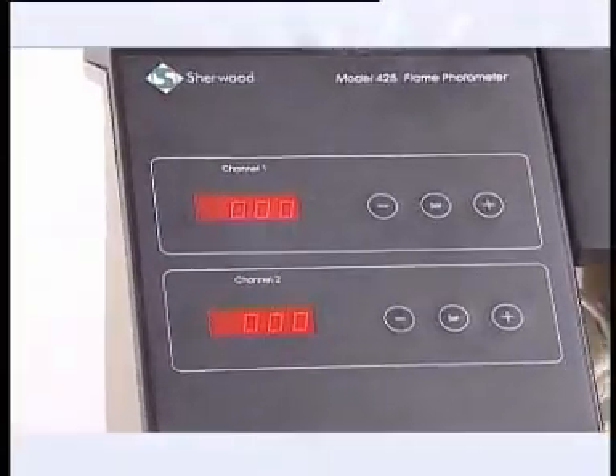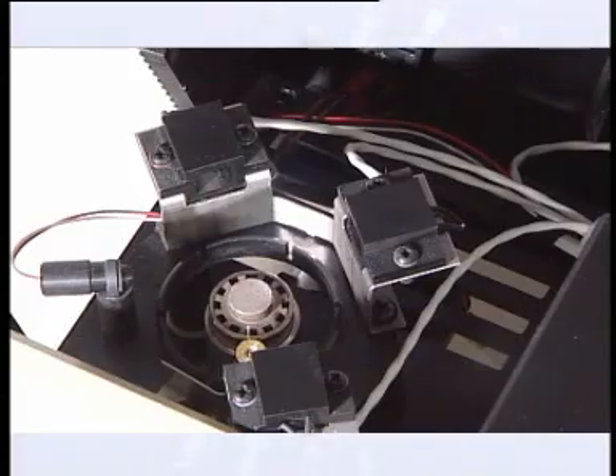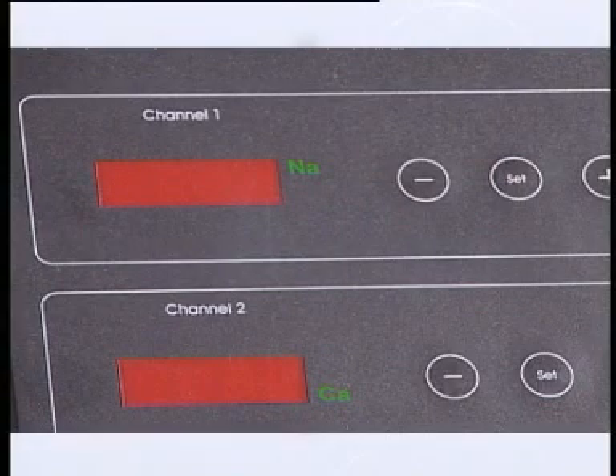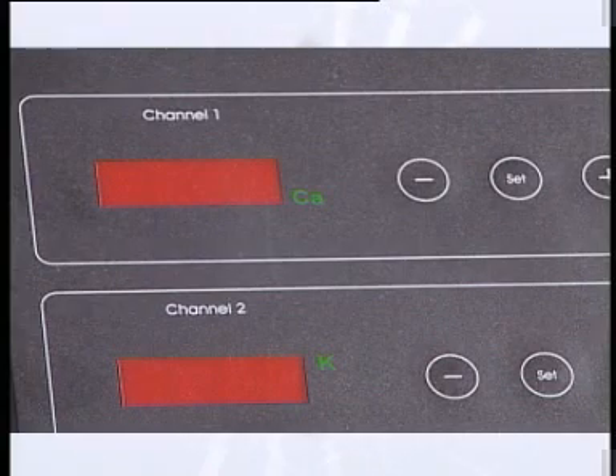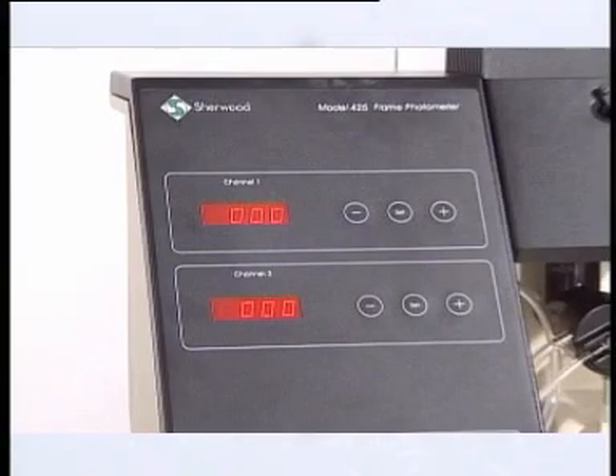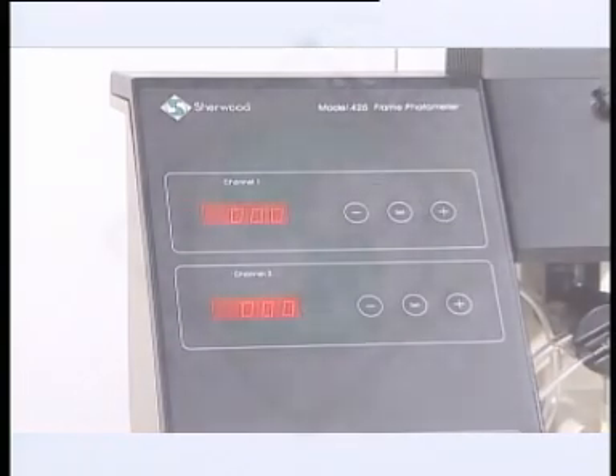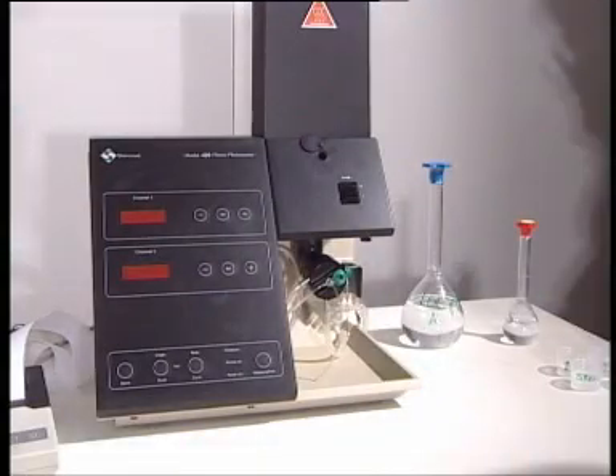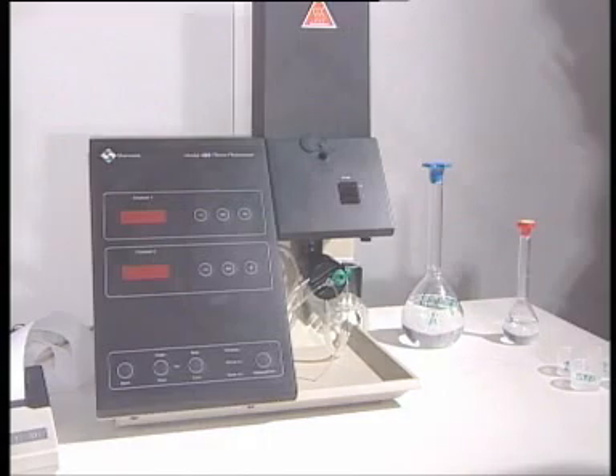In the Model 425 4-element flame photometer, Sherwood Scientific now adds calcium to the menu of elements that can be measured. Calcium can be measured in combination with sodium or potassium, each with lithium internal standard and with lithium. This enables fertilizer and soil extracts to be measured following the appropriate extraction procedures. Please note that calcium cannot be directly measured on clinical samples. Again, a suitable extraction method has to be used. The Model 425 is the only professional flame photometer measuring calcium in conjunction with sodium or potassium.